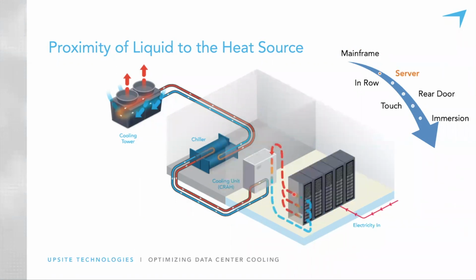So now moving to the server phase of the industry, when IT equipment started to be designed to fit in these discrete U units, the decision was made to switch to air cooling because it's such a flexible solution. All the equipment is immersed essentially in air. You put a fan in it and it's going to suck air in the front and blow air out the back, and it's going to take care of itself and cool itself. Hopefully you're providing the right inlet air temperature to the face of the cabinets, but it's essentially going to take care of itself quite flexibly.